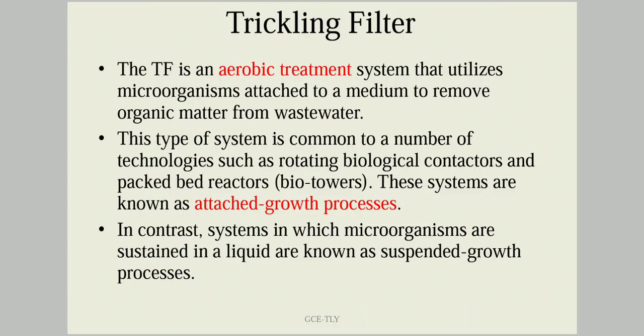In trickling filtration, this is an aerobic method where aerobic bacteria act on the wastewater and oxidize the organic matter into a stable form. The microorganisms are attached to a medium and, while the water passes through, they act on the organic matter. This system is common to technologies such as rotational biological contactors and packed bed reactors, also known as bio towers, and these systems are together known as attached growth processes, since the microbes get attached and grow on a medium.